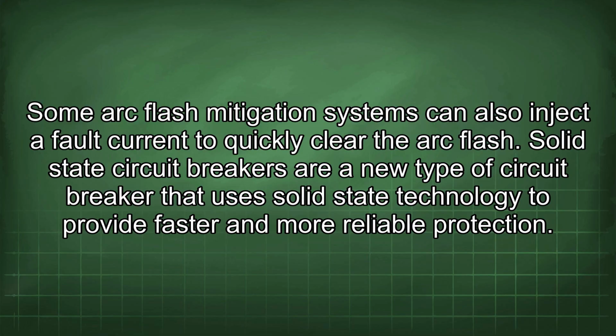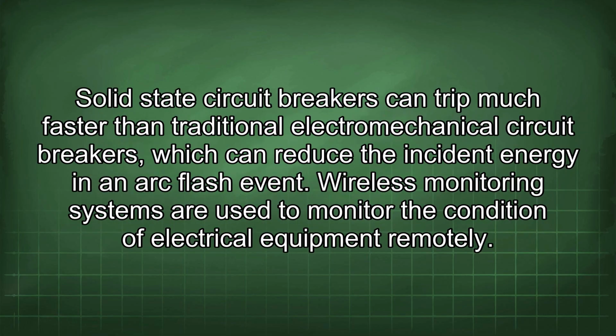Solid-state circuit breakers are a new type of circuit breaker that uses solid-state technology to provide faster and more reliable protection. Solid-state circuit breakers can trip much faster than traditional electromechanical circuit breakers, which can reduce the incident energy in an arc flash event.